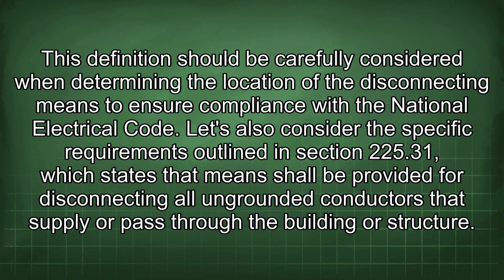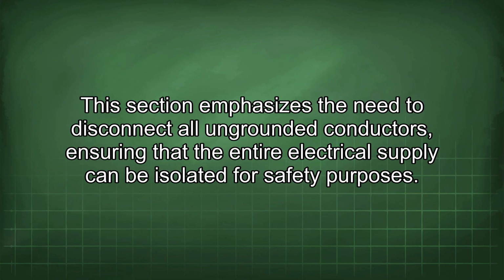Let's also consider the specific requirements outlined in Section 225.31, which states that means shall be provided for disconnecting all ungrounded conductors that supply or pass through the building or structure. This section emphasizes the need to disconnect all ungrounded conductors, ensuring that the entire electrical supply can be isolated for safety purposes.